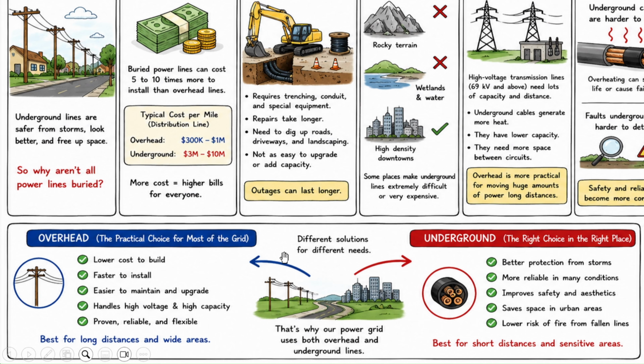Because underground systems are much more expensive to build, as we've seen, and harder to repair. Also, for high voltage lines, you will have heat that will not escape easily underground, which will cause the insulation and the cable to degrade over time.